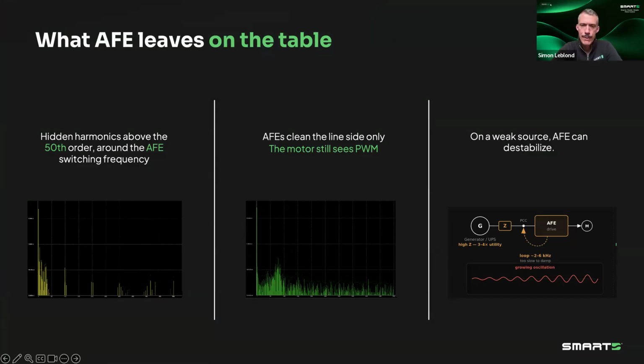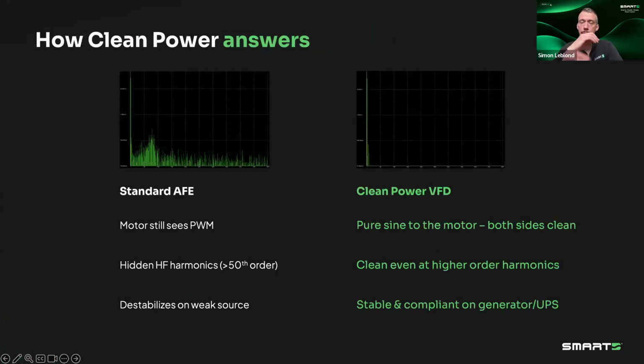I don't have the exact slide for ours, but it would be similar to this one on the right, where because we switch at a much higher switching frequency, all of the higher orders are filtered out by our integrated filters. So you're basically putting your harmonics and your EMI in the same bandwidth and filtering them at the same time. So you get a really clean signature. Not exactly that one, I don't want to misrepresent, but basically absolutely nothing above the 35th order.